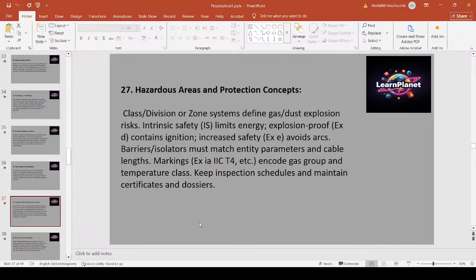Hazardous areas and protection concepts. Class division or zone systems define gas and explosion risks. Intrinsic safety limits energy. Explosion proof contains ignition. Increased safety avoids arcs. Barrier isolators must match entity parameters and cable lengths. Markings like Ex ia, IIC, T4, etc. encode gas group and temperature class. Keep inspection schedules and maintain certifications and dossiers.